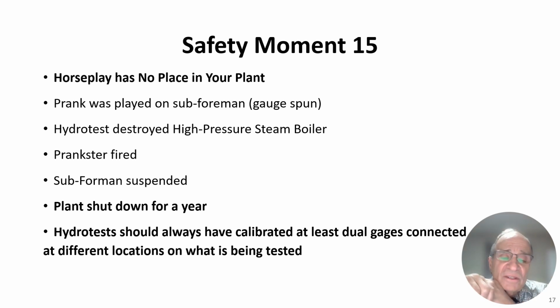There were a couple of things that were wrong here. First of all, hydro tests should always be done with calibrated gauges, so that damaged gauge would have never seen that test had it been calibrated and then brought to the test site. Also, secondly, you have to have at least two separate gauges. Ideally, one a chart recording gauge and the other one a dial gauge, so that you're knowing, and it's connected at two separate locations on the boiler and set up at different locations.